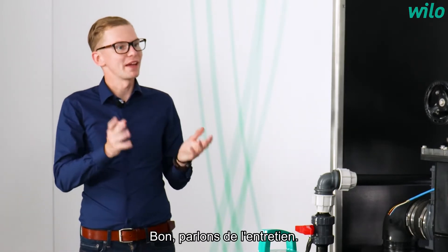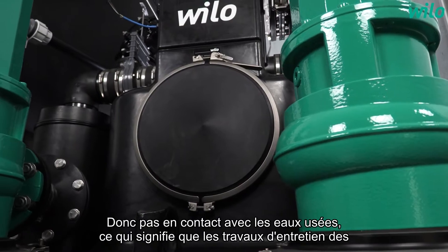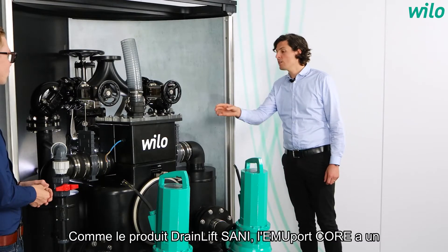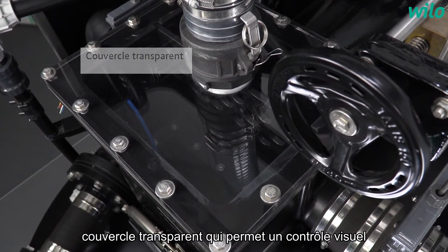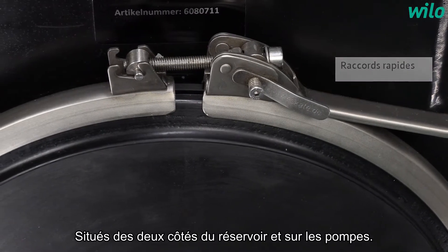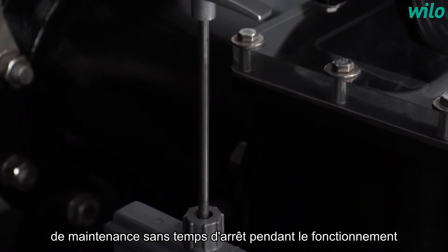Let us talk about maintenance. How is hygiene and maintenance made easy here? The pumps sit outside of the enclosure and therefore not in the medium, which means that maintenance work to the pumps can be conducted quickly, comfortably and hygienically. Similar to the DrainLift Sani product, EmuPort Core has a transparent cover with which a visual check can be conducted during operation. Opening and closing the system is easy via the quick connectors. And for both sides — the solids separation tank and pumps — there's a shutoff, which enables maintenance work to be conducted without downtime during the operation of the product.